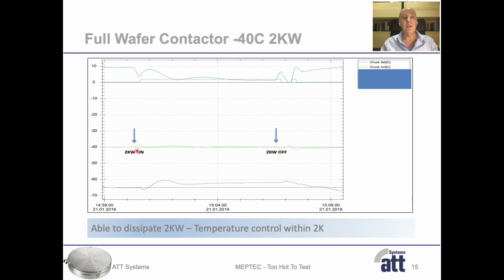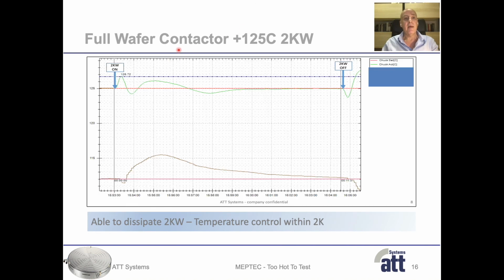When we turn on the 2000 watt, the temperature will increase, in this case by around 2 degrees C, and then the system is able to fully dissipate the 2000 watt and to control the temperature at the set point. So also at minus 40 degrees C, we are able to dissipate 2000 watt and to control the temperature within 2 Kelvin. And then the last test for the full wafer contactor at plus 125 degrees C, and exactly the same picture. In this case, the temperature increases to 126.7 degrees C when applying the 2000 watt, and then the system can fully dissipate the energy and can control the chuck temperature very close to the set value.